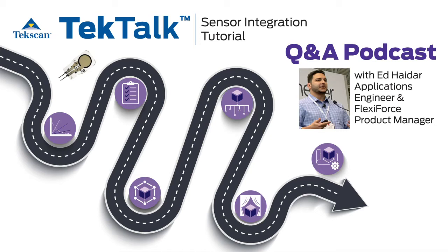Why are you applying a square waveform into your reference voltage to your sensor? That's a great question. It doesn't have to be a square wave. It can be a DC voltage or a constant voltage. Generally, the sensors are a semiconductive material, and under higher voltages, and when I say higher voltages, I'm talking in terms of something above 1 to 1.5 volts, you can start to affect the sensor's lifespan.